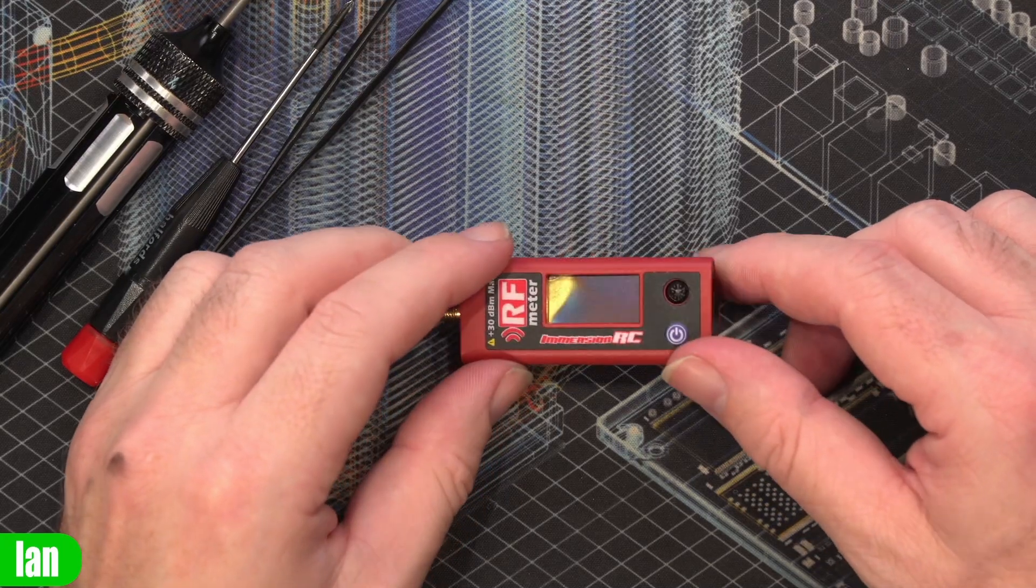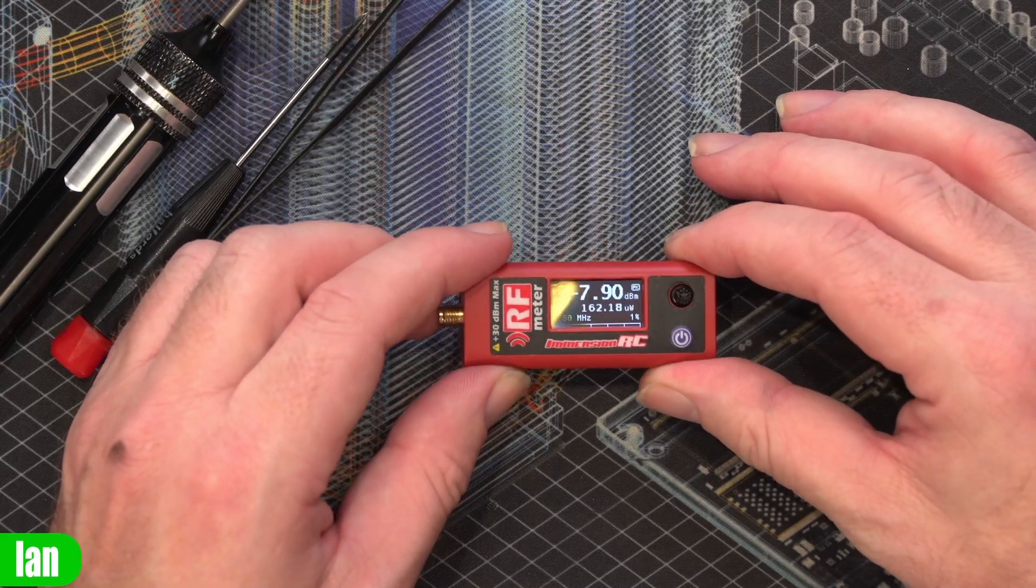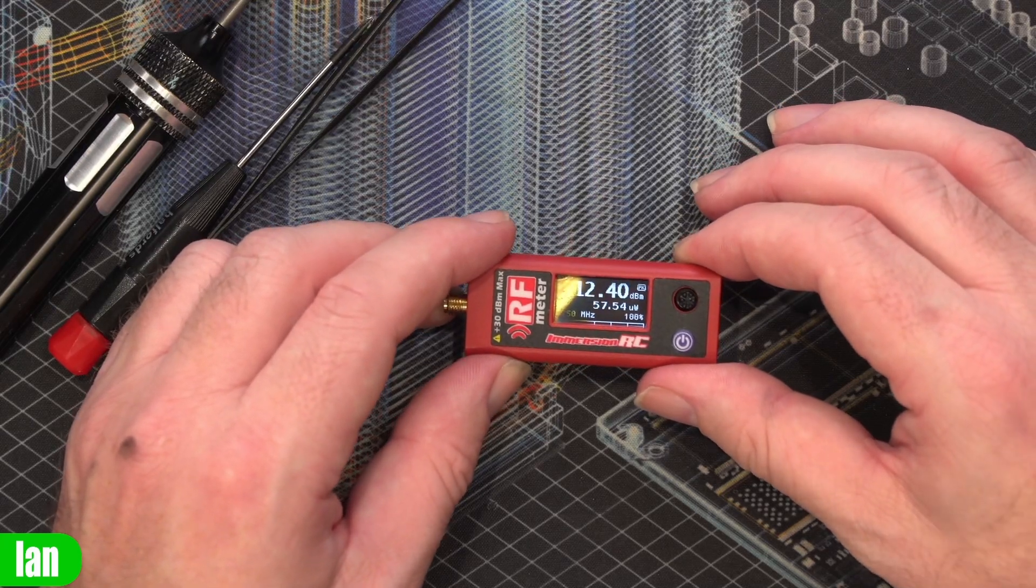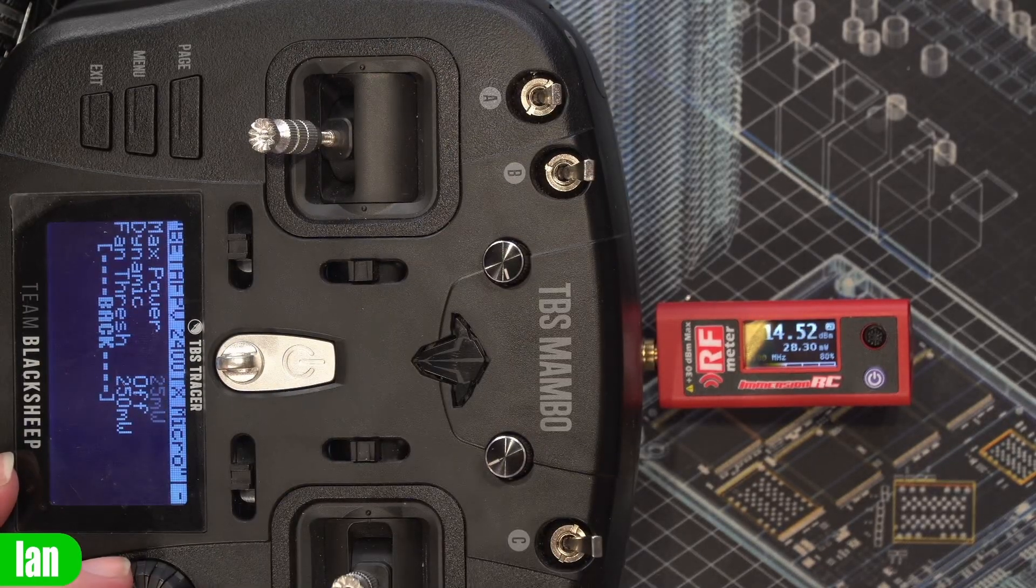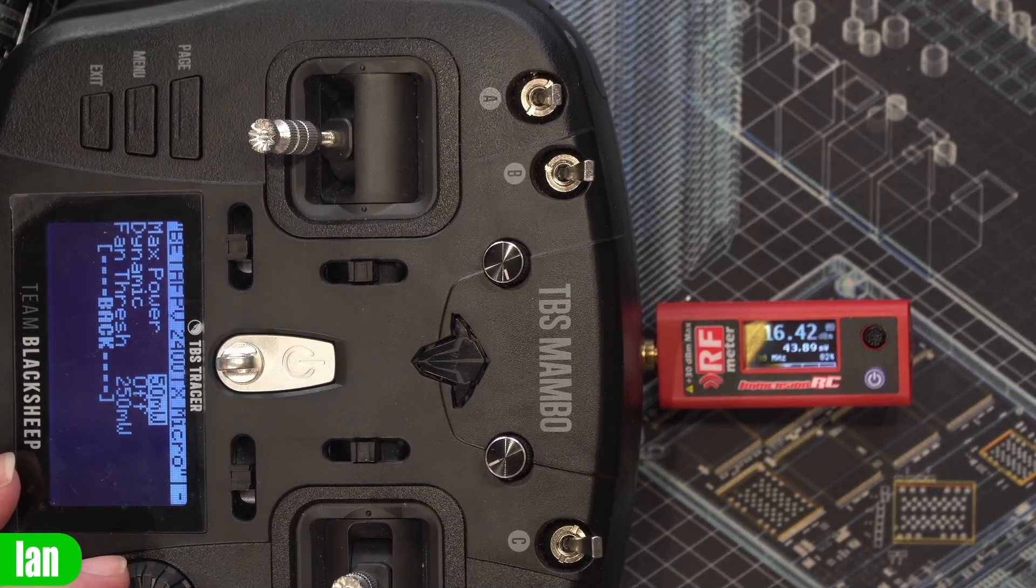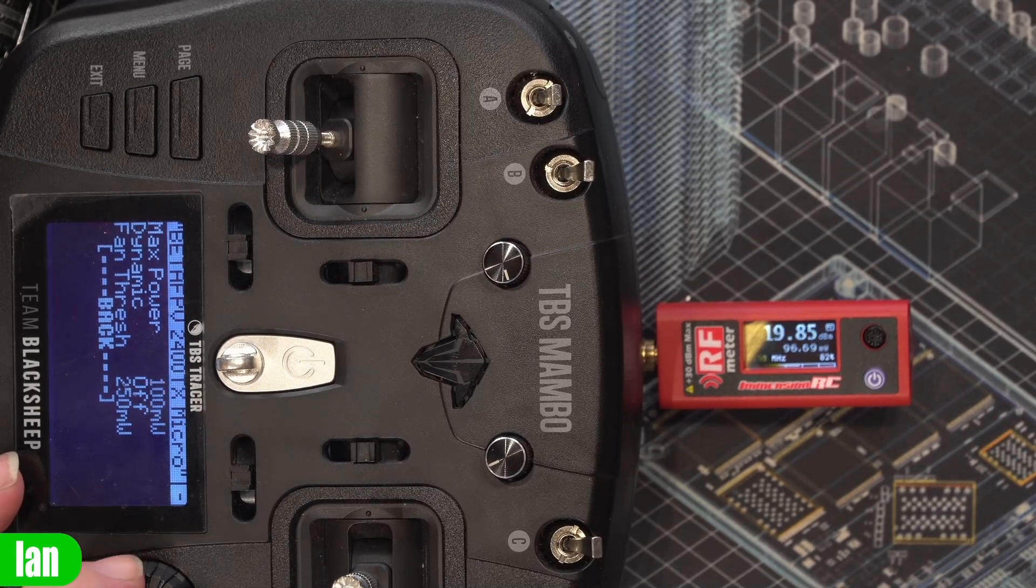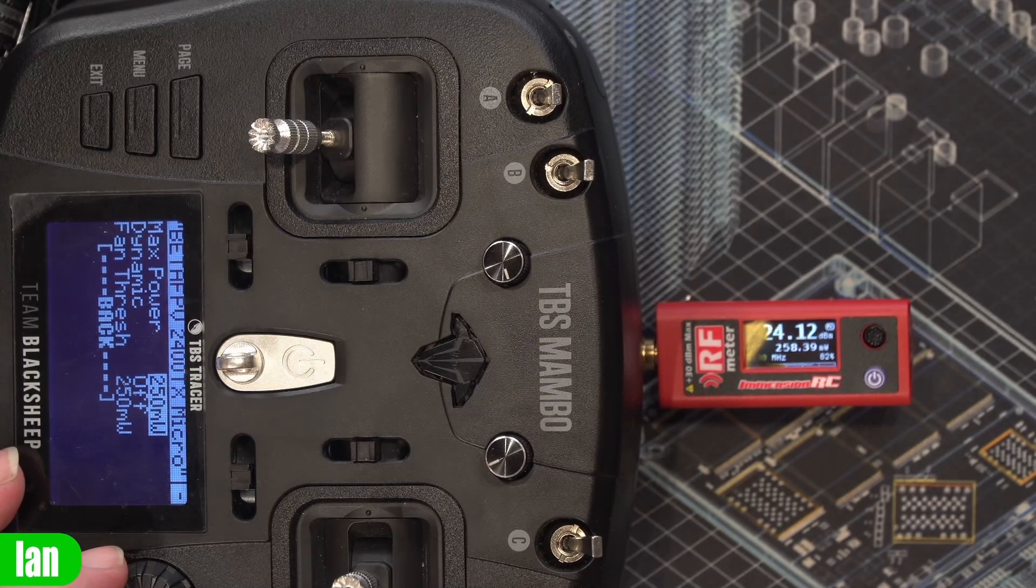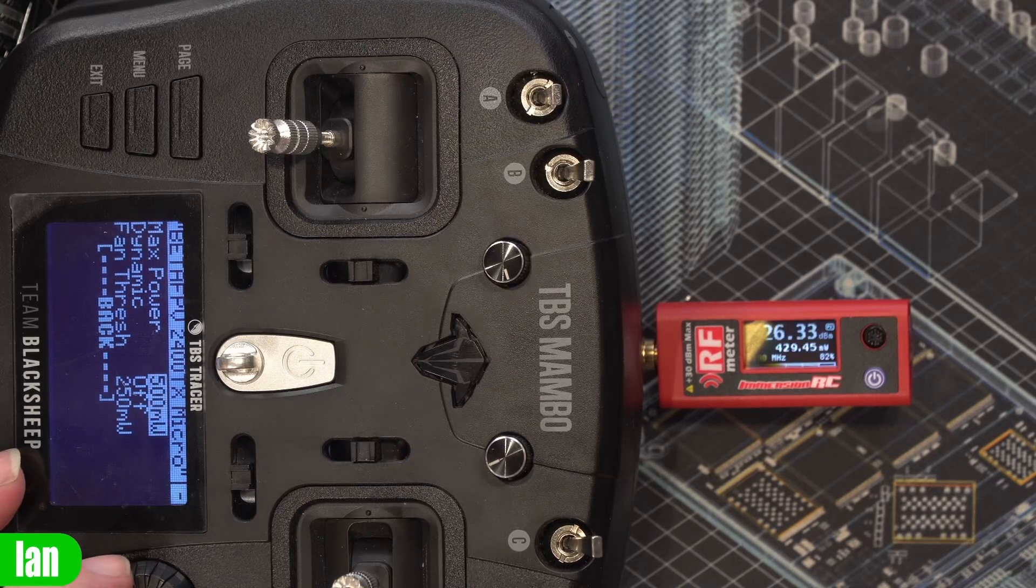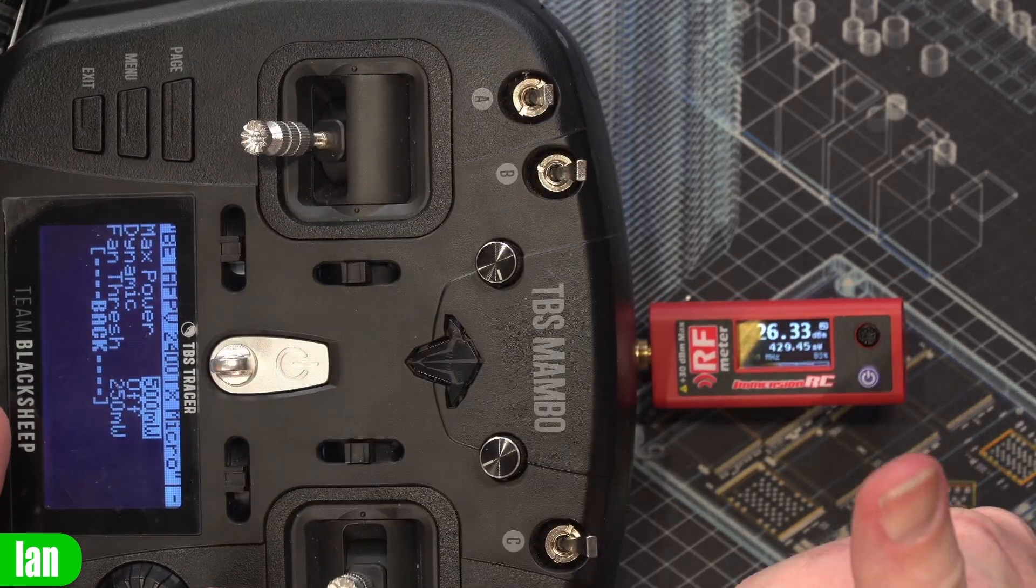So it's back together. Let's see if it's actually working properly. Test it against my known readings already. On 25 we're seeing 28. On 50 we're seeing 43. That's very close. On 100 we're seeing 98, 99. On 250 we're seeing 260. That is very close. And on 500 we're seeing 429, which is virtually bang on with the readings I was getting on it before. So we're still good.